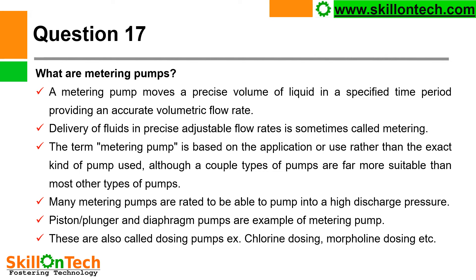What are metering pumps? A metering pump moves a precise volume of liquid in a specified time period, providing an accurate volumetric flow rate. Delivery of fluids in precise, adjustable flow rates is sometimes called metering. Many metering pumps are rated to pump into high discharge pressure. Piston, plunger, and diaphragm pumps are examples of metering pumps. These are also called dosing pumps — for example, chlorine dosing, morpholine dosing, etc., in industries.